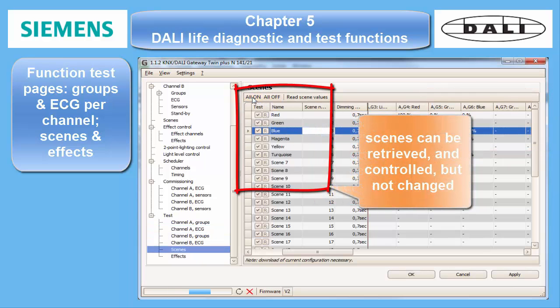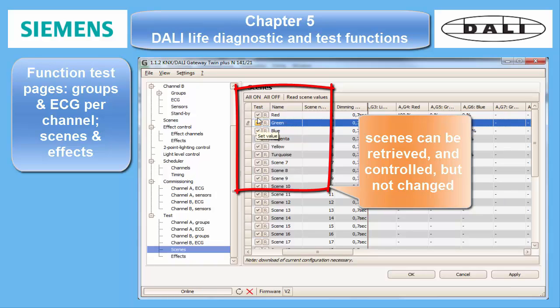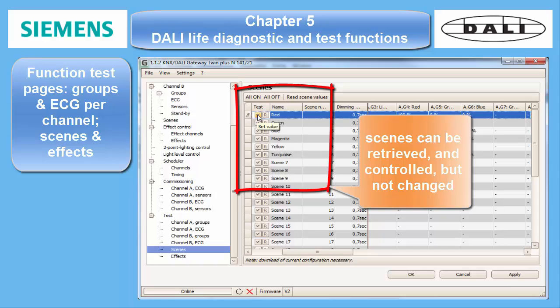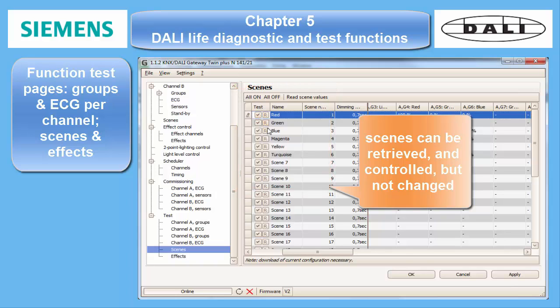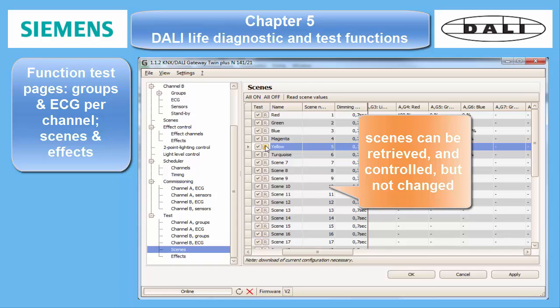The scene test panel can also control all lights on and off and the individual scenes. It can also read scene values which might have been changed in the meantime by the user. Changes, however, cannot be applied here. They must be made in the configuration dialog and downloaded again.